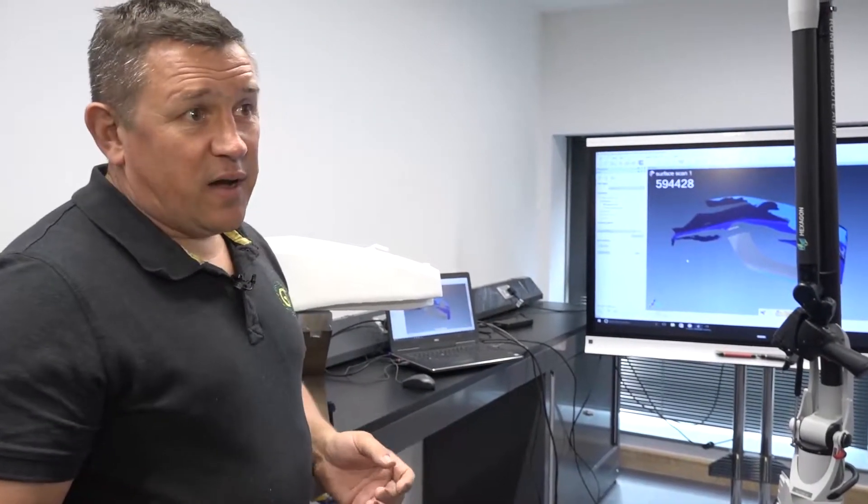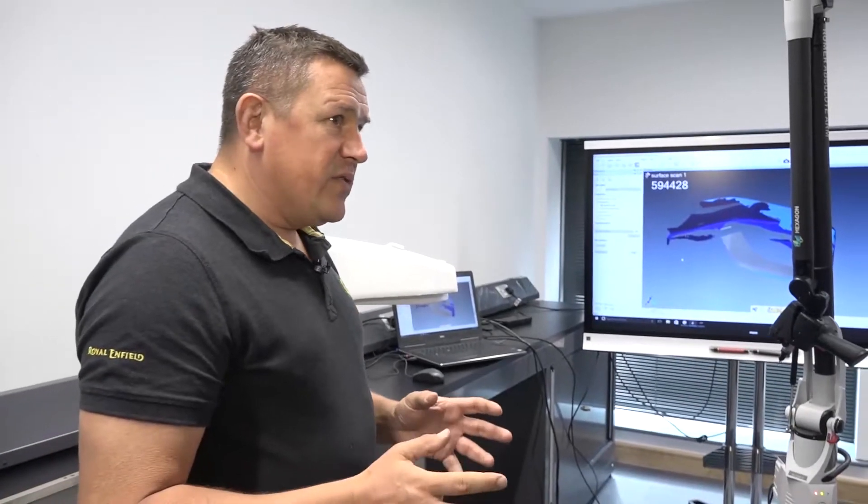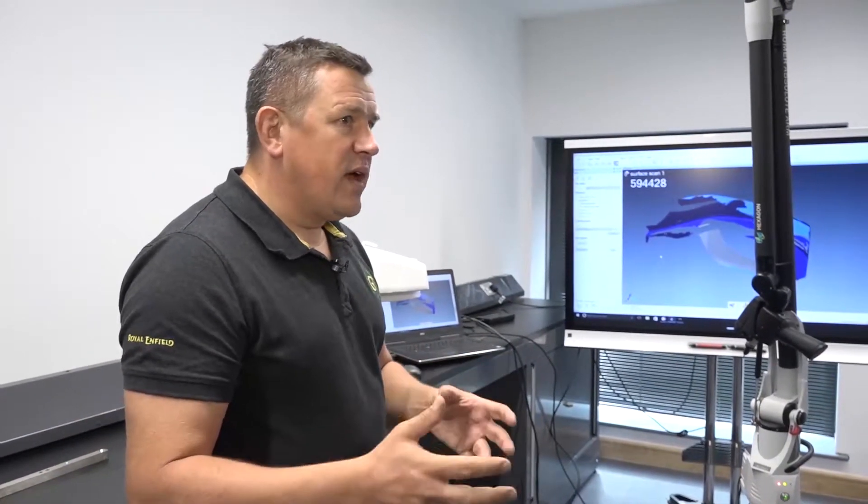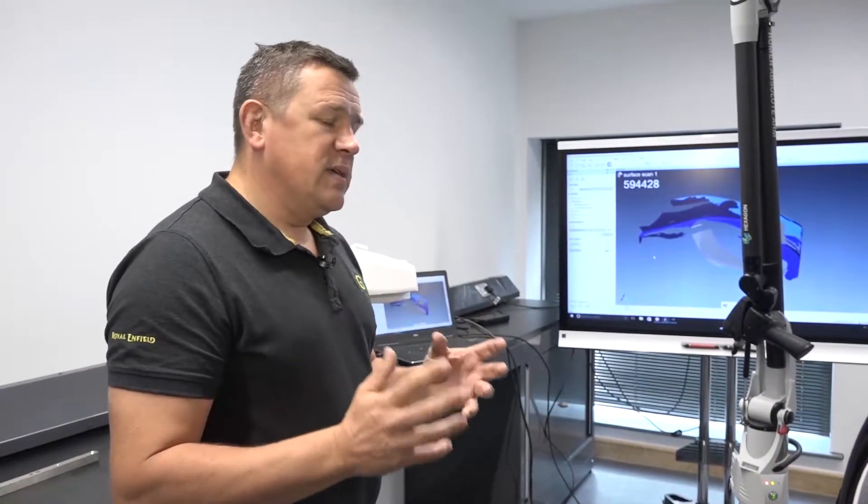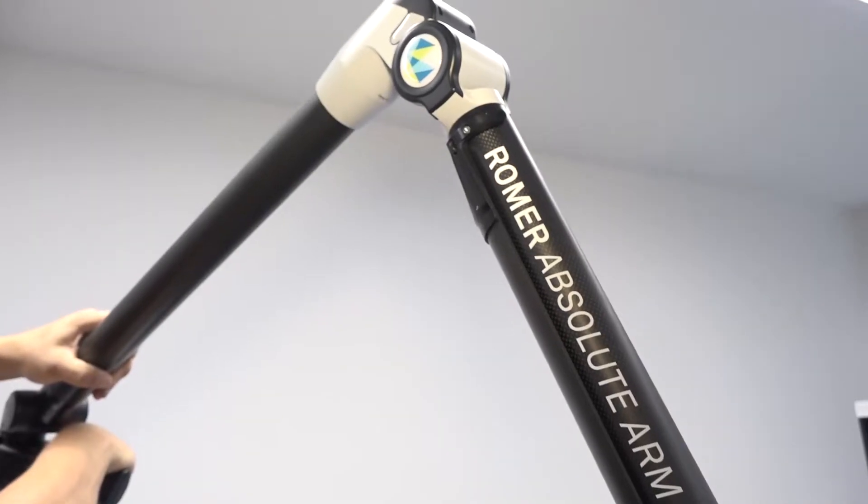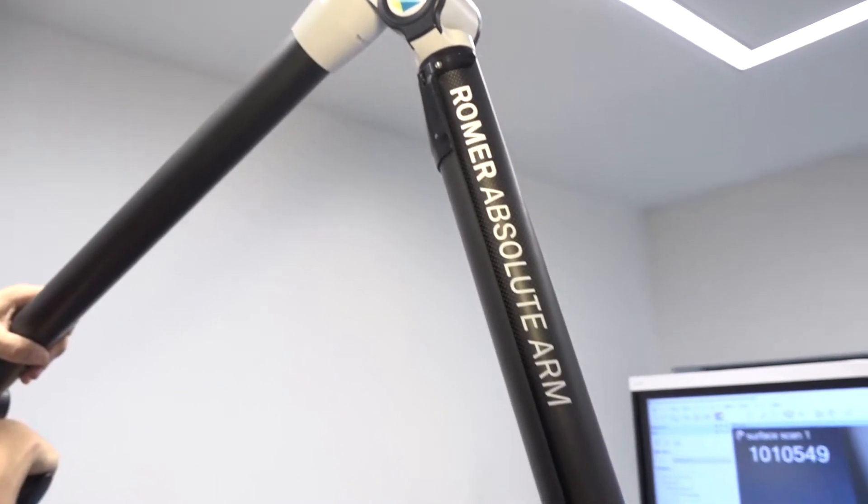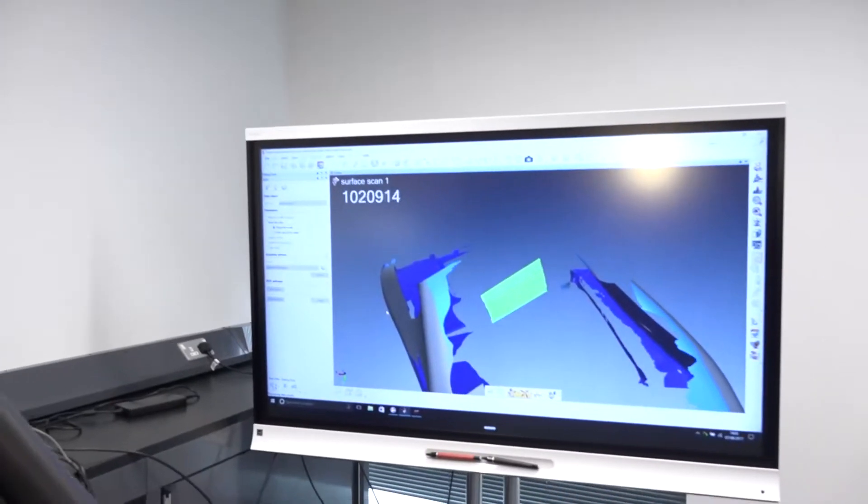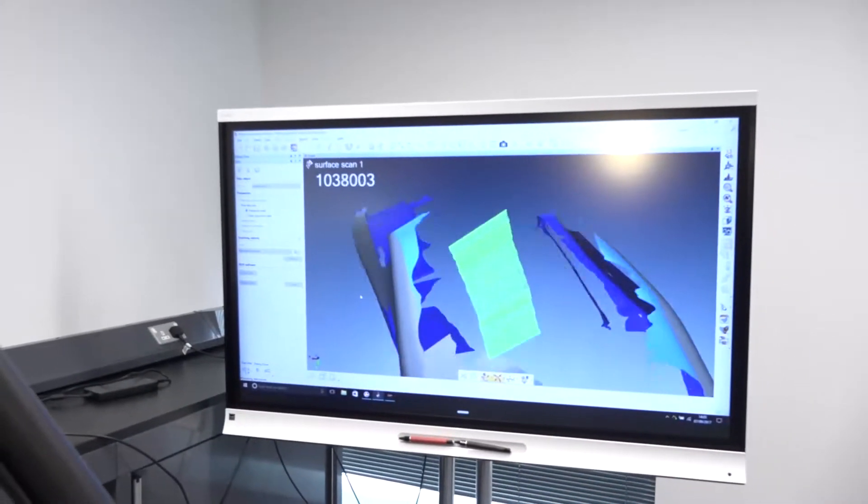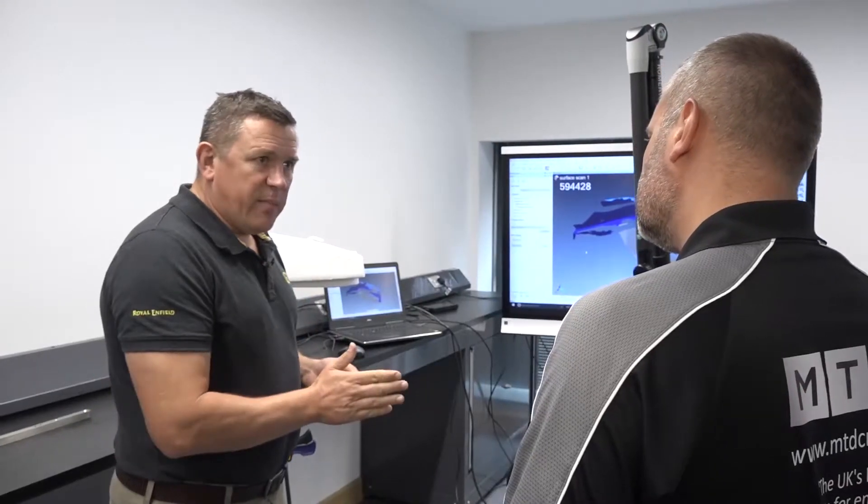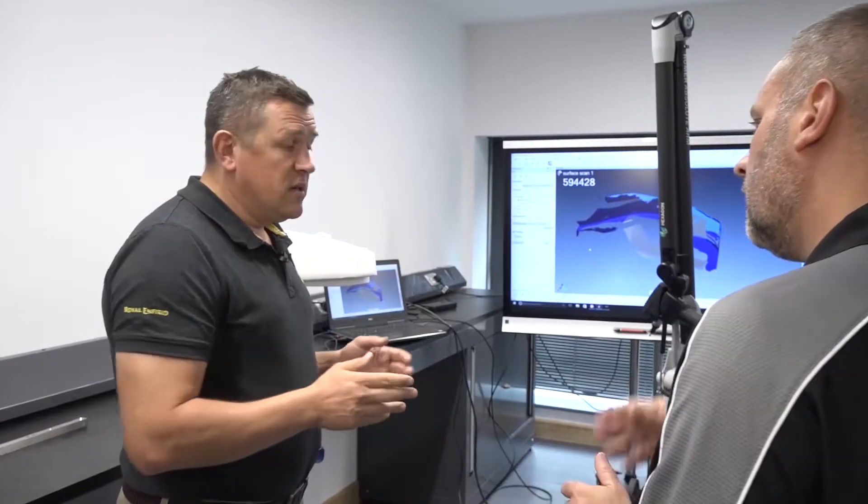Other units on the market at the moment, I haven't got that confidence with. I'm sure they're very good units, they're great. But my quality brain is saying to me, is this measurement right? This unit comes with its own calibration bar. It allows me to go straight to the calibration unit, check that calibration, and it removes that point from my calculations.